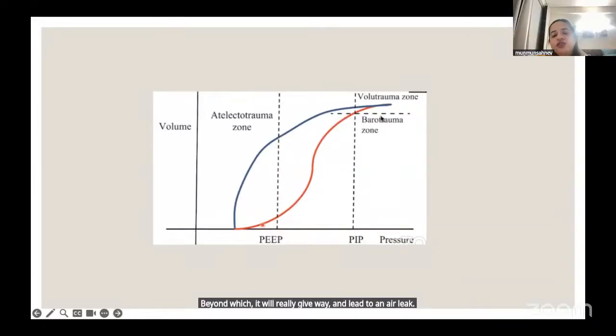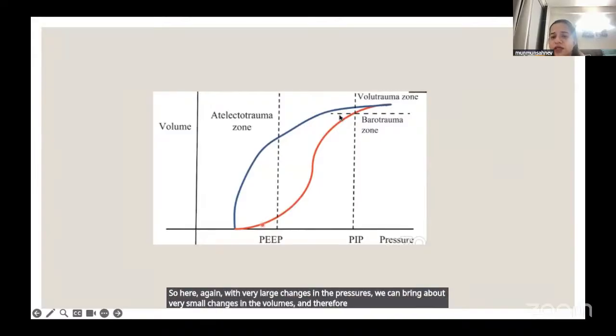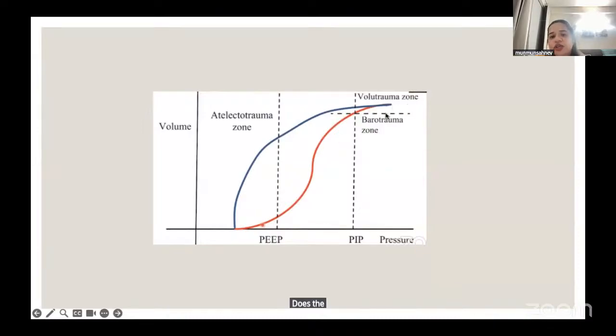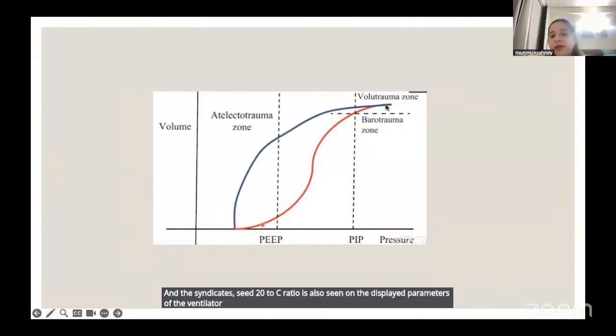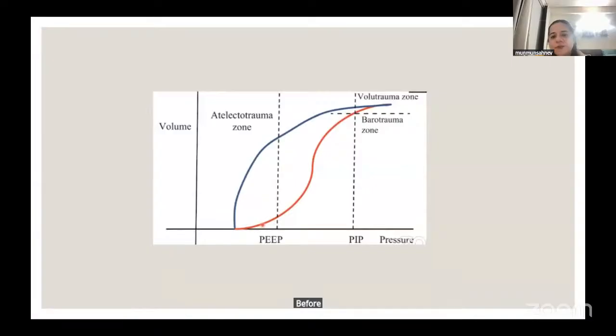It approaches this phenomenon which is called air leaking. So here again, with very large changes in the pressures, we can bring about very small changes in the volumes, and therefore the compliance has reduced drastically. Thus, the C20 to C ratio is always less than 1. The C20 to C ratio is also seen on the displayed parameters of the ventilator. Being less than 1 indicates hyperinflation and the phenomenon of beaking, which can sometimes happen before the stage of pneumothorax.